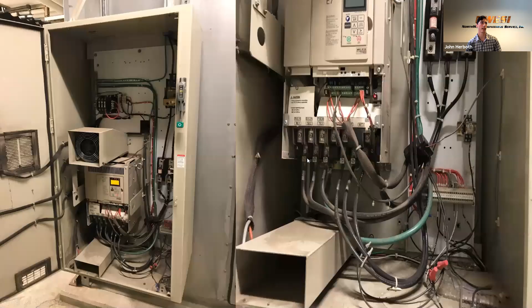Some big air handlers on the top, that's what you're seeing right here. Inside of it were some landings from the fire alarm system, but nothing was shutting down. On an older system like this, an older VFD, you have to get a rep out to take a look at it because, as often as we look through VFD settings and know our way around quite a few different controllers, this was one I had no clue what was going on here. All I know is it wasn't working.